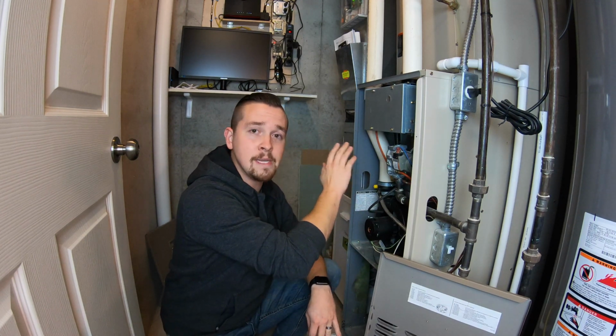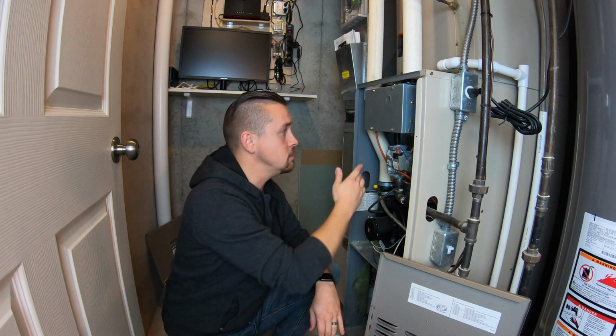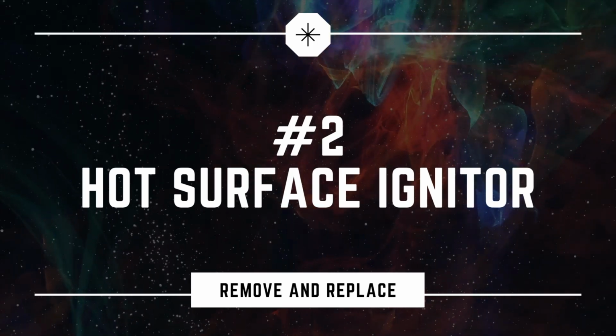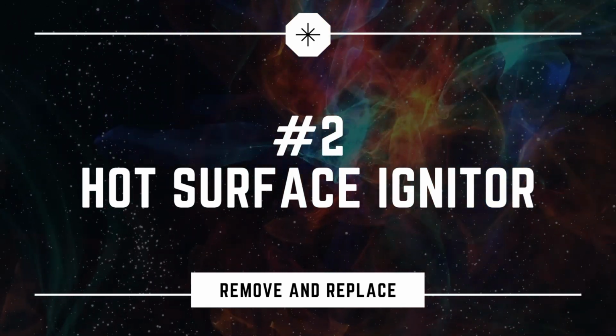And that's because the flame sensor can no longer sense flame. So you just need to pull it out of there, clean it with a cloth, a dollar bill. I use a bronze brush. I know I said it in my other video, but I'm gonna say it again. Do not use sandpaper to clean your flame sensor. Don't do it. Number two is a broken hot surface igniter.